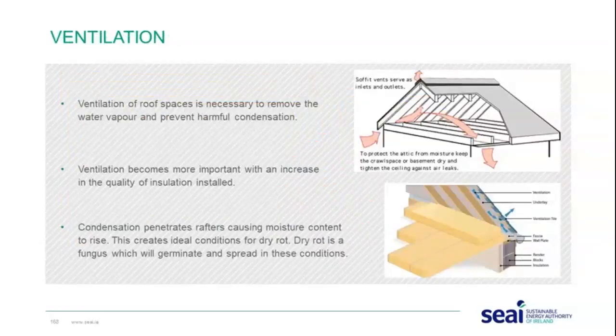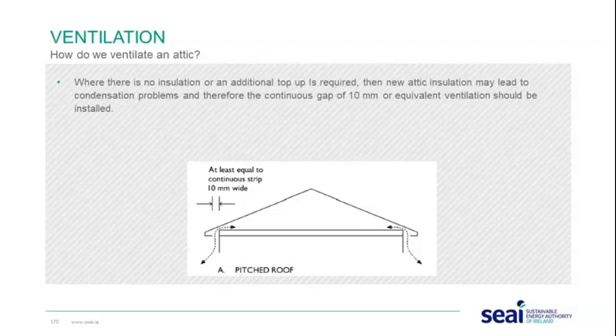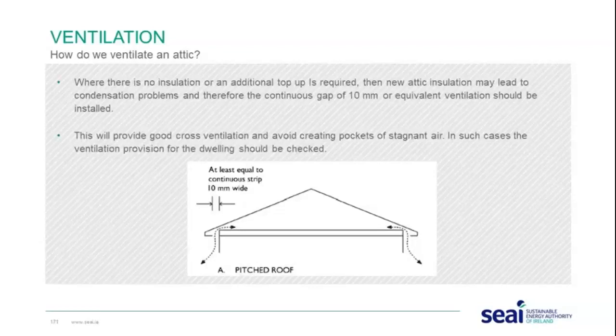Ventilation in the roof space is necessary to remove water vapour and prevent harmful condensation. Ventilation becomes more important with the increased quality of insulation used. Condensation penetrates rafters causing moisture content to rise, creating ideal conditions for dry rot — a fungus which can germinate and spread in these conditions. Where there is no existing insulation or a top-up is required, new attic insulation may lead to condensation, and therefore a continuous gap of 10 millimetres or equivalent ventilation should be installed.